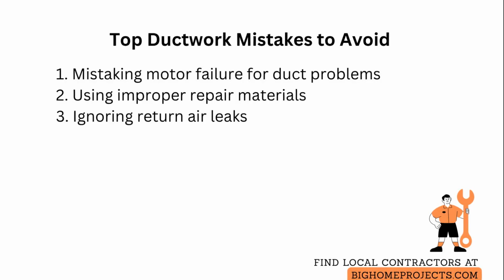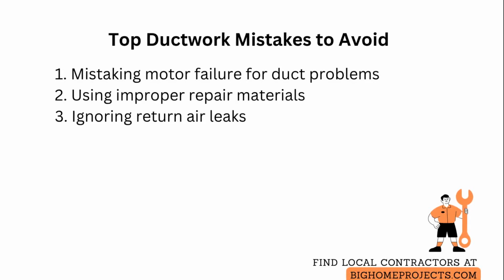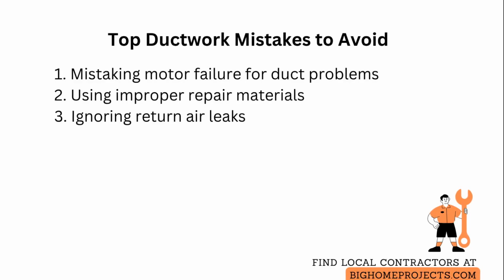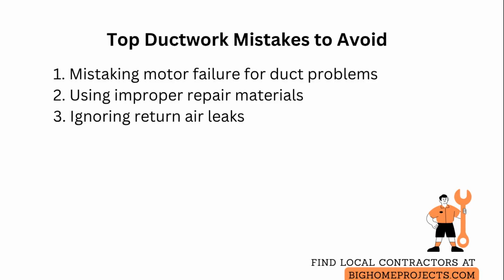A third concern is ignoring return leaks that let unconditioned air bypass the system and change blower pressure. Locate gaps with a smoke pencil or pressure testing and close them, then recheck system balance.